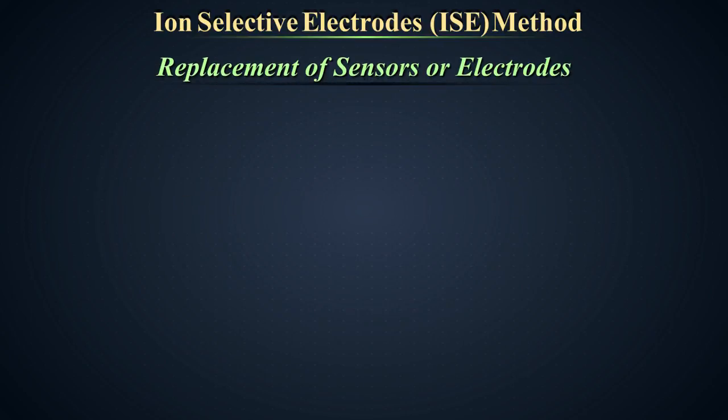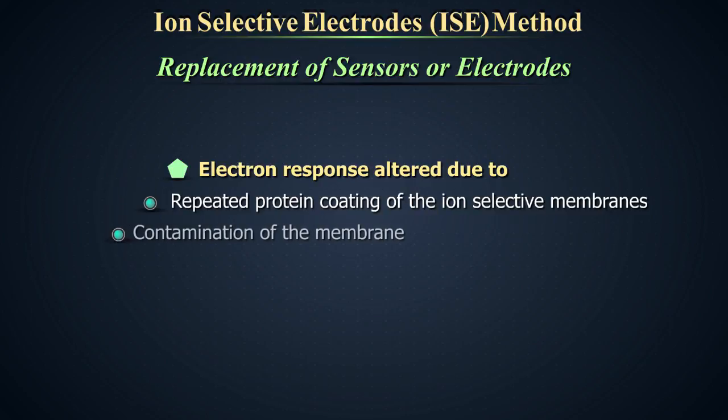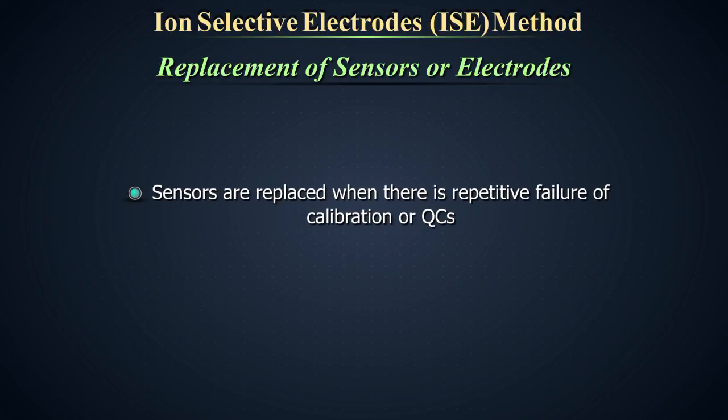Replacement of sensors or electrodes. Repeated protein coating of the ion-selective membranes, contamination of the membrane, salt bridge formation by ions can all alter electron response. These necessitate periodic changes of the membrane as part of the routine maintenance. The sensors should be considered for replacement if there is a repetitive failure of calibrations or quality controls.